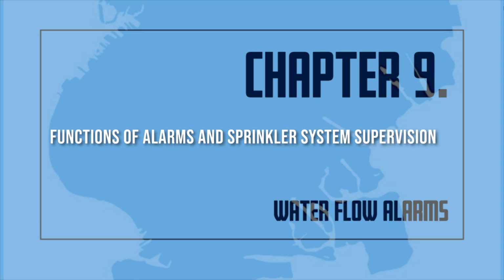Sprinkler systems are required to have an approved water motor gong or an electric bell, horn, or siren on the outside of the building. An electric bell or other audible signal device may also be located inside the building. Water-operated devices must be located near the alarm valve, dry pipe valve, or other water control valves in order to avoid long runs of connecting pipe.